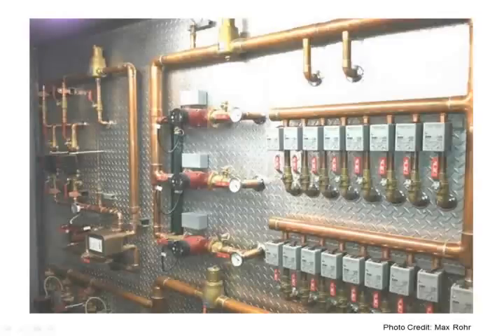I don't see any dirt separators on this job. Perhaps there is. Perhaps this is new construction. It wasn't so much an issue. But what happens if we have corrosion in our system? And basically, the effects of that corrosion causing debris to get into, well, it could get into our heat exchanger. It could get into our boiler. If this is a cooling system, it could get into our chiller.